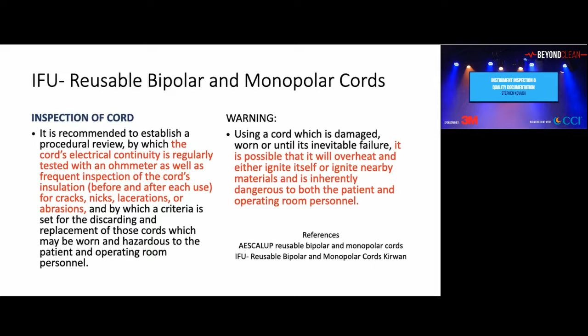It is recommended to establish a procedure by which the cord's electrical continuity is regularly tested with an ohm meter, as well as frequently inspecting the cord's insulation before and after each use for cracks, nicks, and abrasions. Using a cord which is damaged or worn, until it inevitably fails, it is possible that it will overheat and either ignite itself or ignite nearby material, which is inherently dangerous to both the patient and operating personnel.